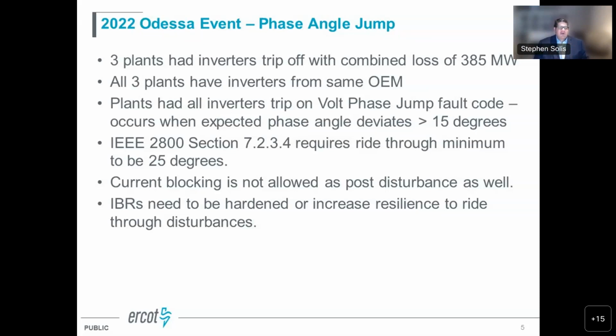Some other things just to note: current blocking is not allowed post-disturbance as well in that section. And in general, IBRs need to be hardened or increase resilience to ride through these types of disturbances. I do encourage, and this one's a little bit of a different situation, but if the requirement's 25, but your equipment can do 45, sometimes you want to go ahead and utilize that additional equipment capability. Don't just go for the bare minimum if it increases the resilience.